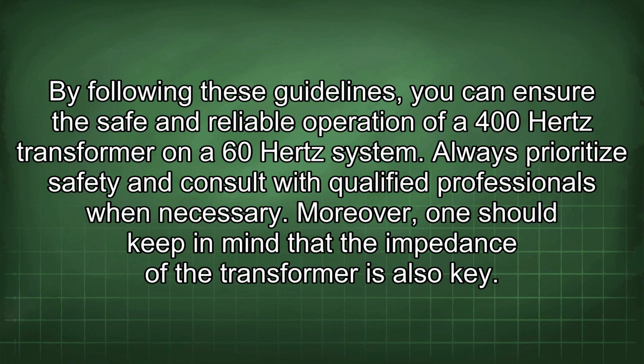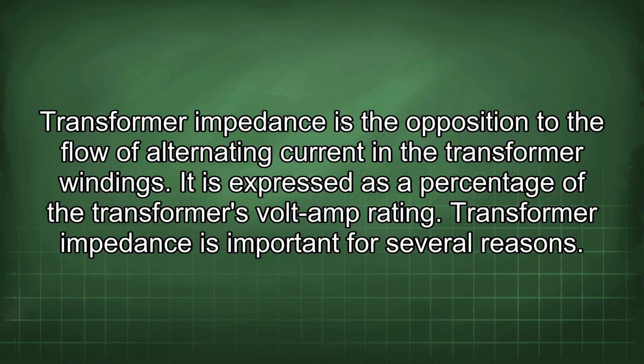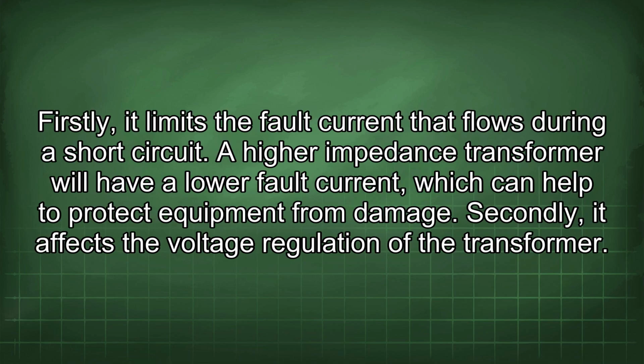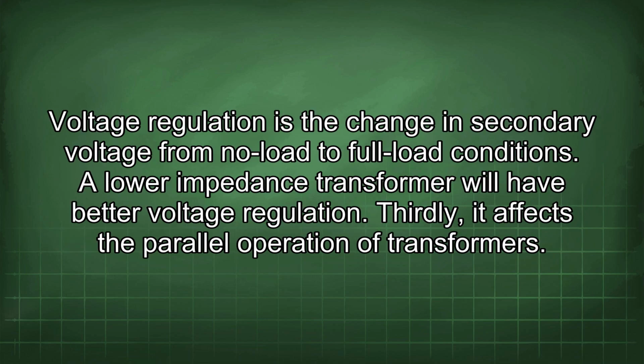Moreover, one should keep in mind that the impedance of the transformer is also key. Transformer impedance is the opposition to the flow of alternating current in the transformer windings. It is expressed as a percentage of the transformer's volt-amp rating. Transformer impedance is important for several reasons. Firstly, it limits the fault current that flows during a short circuit. A higher impedance transformer will have a lower fault current, which can help to protect equipment from damage. Secondly, it affects the voltage regulation of the transformer. Voltage regulation is the change in secondary voltage from no load to full load conditions. A lower impedance transformer will have better voltage regulation.